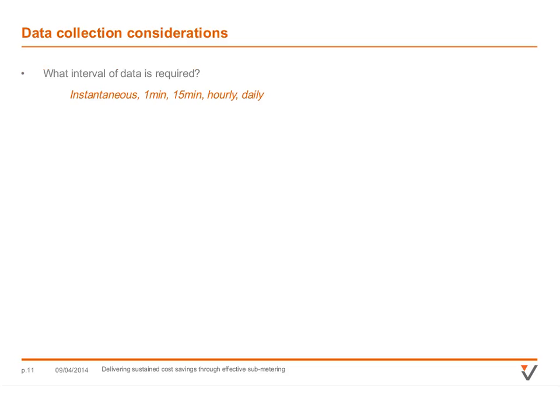What interval of data is required? Sometimes there's instantaneous, in something like a SCADA application - that's when you've got something really process critical and need to know exactly what's happening all the time. You could then have maybe 1 minute data, which is still quite a high interval. Then it could be anything, but typical ones are 15 minute, then maybe half hourly, hourly, daily, monthly. Really think about what interval data you need and how you use it - when you spot a problem, would 15-minute data be enough to establish what's gone on? Because the price of the technology to capture this can change quite a bit depending on what's actually required, so it's always worth thinking about that.